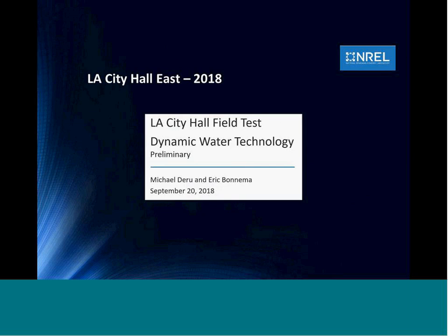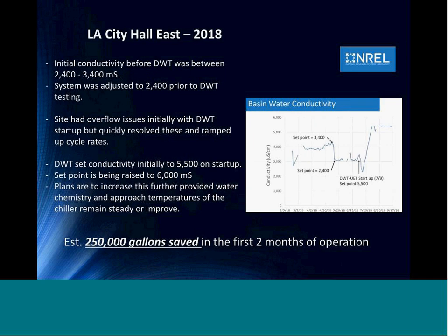As I mentioned, NREL is actually monitoring the process for us. Michael DeRue is a PhD researcher for the Department of Energy out of Colorado and was brought in early on. Next slide. He's been monitoring a number of different elements in the process. When we started the baseline analysis, the initial set point the chemical water treatment company had set had some variability. They were at 3,400 and then had dropped it to 2,400. We believe that was due to the increasing mineralization of the water, but we're not exactly sure why they chose to drop that cycle rate.